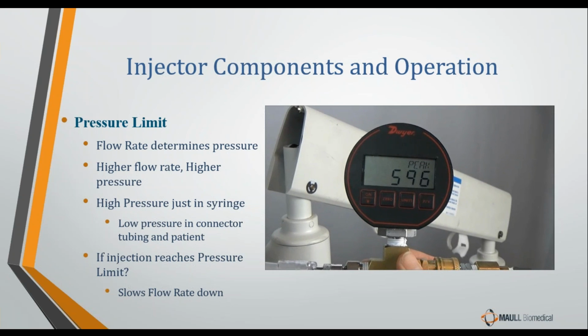So the purpose of that video was just to demonstrate that the primary thing that determines how much pressure is built up in the syringe during the injection is the speed of the injection, the flow rate. The whole purpose of the pressure limit is to set the maximum pressure that we will allow in the syringe during the actual injection. If we set the pressure limit to 600 psi, we're telling the injector, no matter what, don't exceed 600 psi in the syringe during the injection.